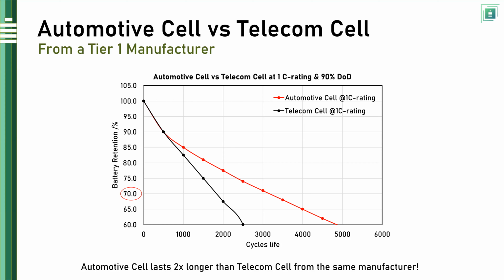Looking at this slide, it's from the same tier 1 cell manufacturer, illustrating cell cycle life. Same manufacturer, but one cell is the Automotive cell and the other is the Telecom cell. At a 1C rating, which is a high charging rate, the Automotive cell has nearly double the cycle life of the Telecom cell. So getting back to my first point, you really want to go with a manufacturer that offers the highest quality cells, because it enables the battery to last the longest.